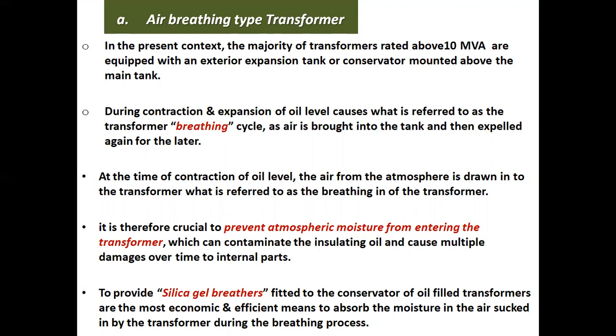At the time of contraction of the oil level, air from the atmosphere is drawn into the transformer, which is referred to as the breathing in of the transformer. It is therefore crucial to prevent atmospheric moisture from entering the transformer, which can contaminate the insulating oil and cause multiple damages over time to internal parts. Silica gel breathers fitted to the conservator of oil-filled transformers are the most economic and efficient means to absorb the moisture in the air sucked in by the transformer during the breathing process.